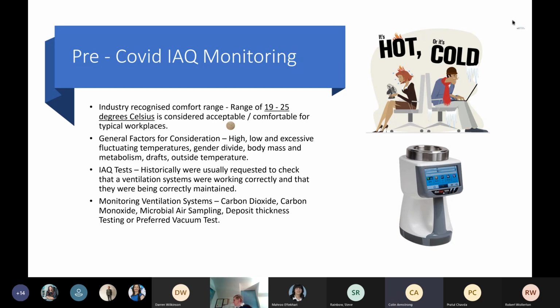So, the monitoring and ventilation systems. Typically, pre-COVID, a client would contact or invite us to undertake a survey of a ventilation system, and it would usually be after they've had a complaint from a member of staff about a dirty grill, an engineer changing filters who has observed dirty ductwork, or maybe the AHU had broken down and an attending engineer had commented on the condition. However, the survey would only be to get an understanding of how dirty a system might be. They were never really looking at the air quality.